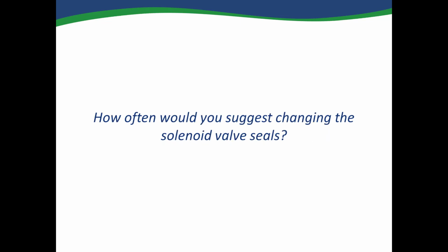Typically, you should never have to change your solenoid valve seals. If you flush the valves regularly, there is a service procedure found on our website for cleaning the valves, and the valves should last indefinitely. There should not be any reason to change the valve seals.